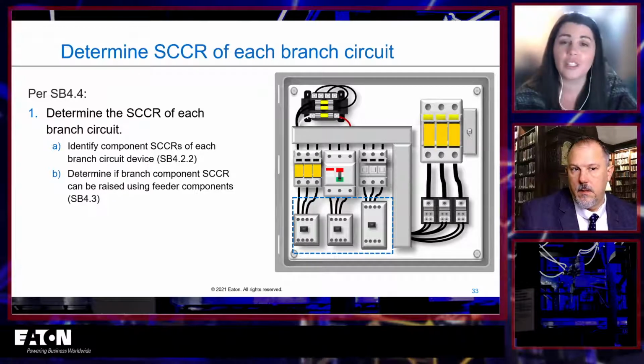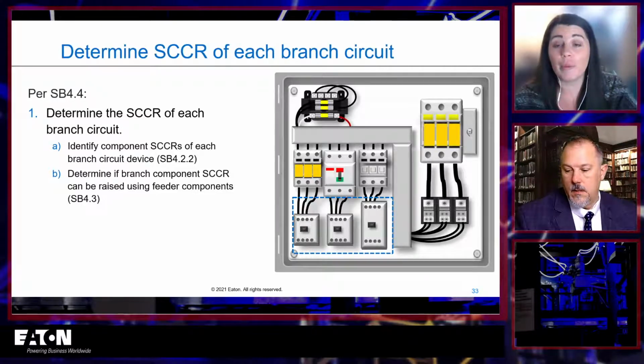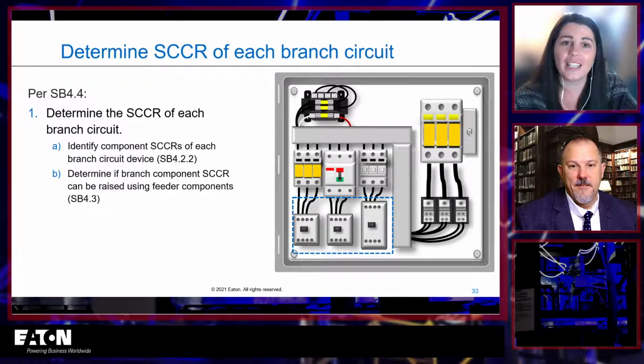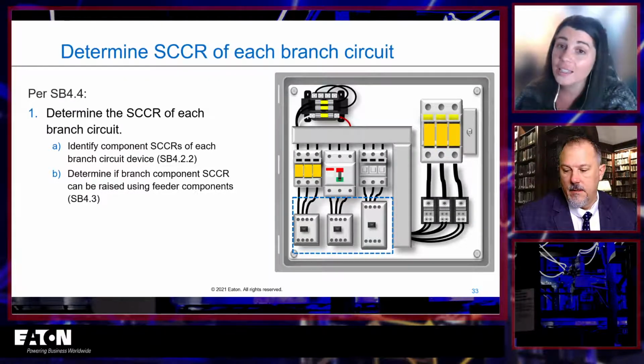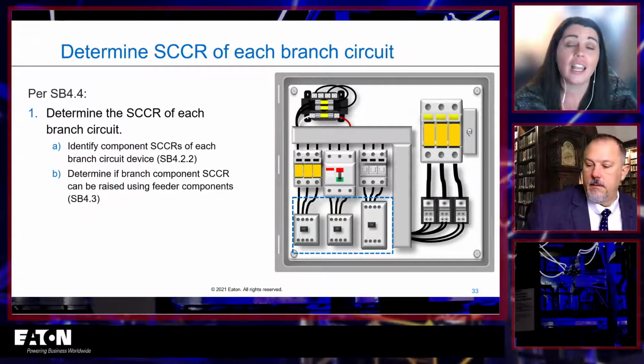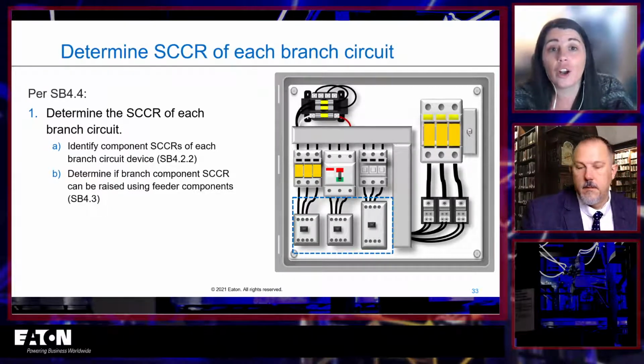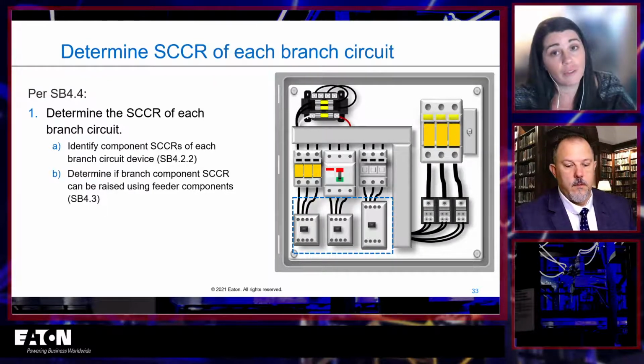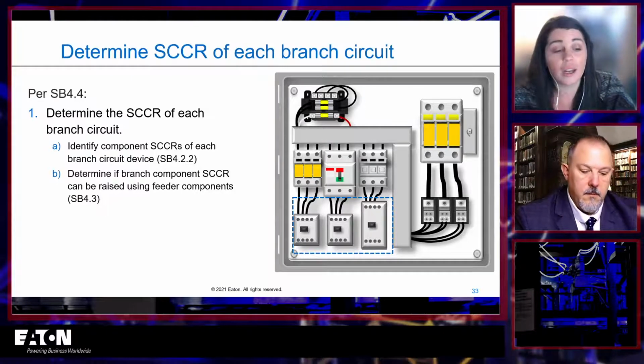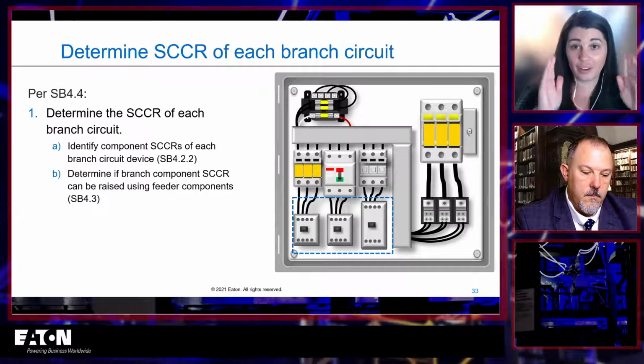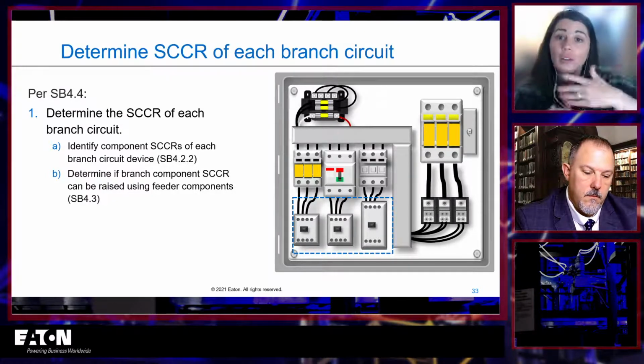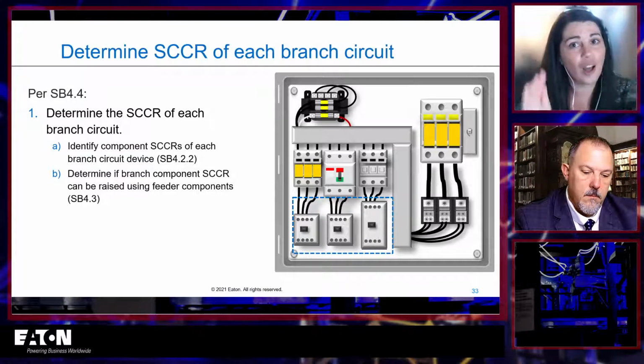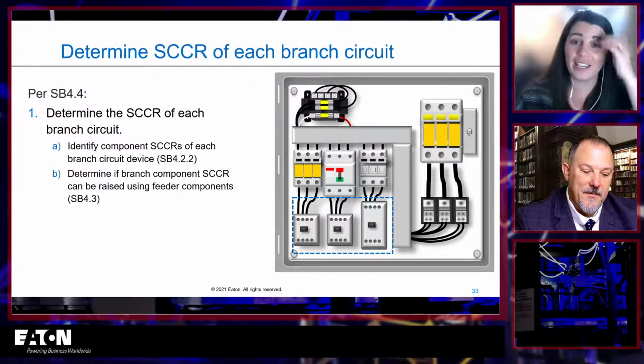is an interesting part of UL 508A because a lot of people don't know it and don't use it at all. And a lot of people use it incorrectly. It's saying that you can actually raise the component short circuit current ratings if you have a current limiting device in your feeder. So that could be a current limiting breaker, it could be a current limiting fuse. That device in your feeder, you can raise it. What this does not say, very importantly, is that you have a main fuse in your panel, you have a 200 kA rated panel. That is not what this says. It's a lot more complicated than that.